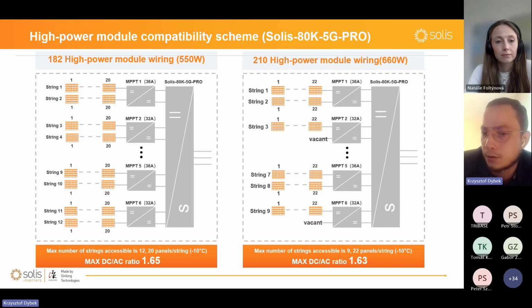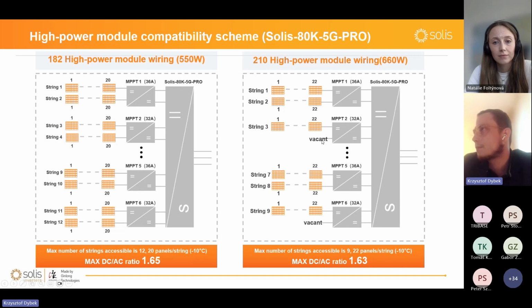Those with 32 amps should be connected with only 1 string, as normally you should avoid paralleling strings if they have different numbers of panels. Otherwise, you can risk string current backfeed. So yeah, the case is like this: 22 panels on the higher, and if you have this MPPT with a little bit less amps, this should remain vacant. That's why you have only 9 strings connected.